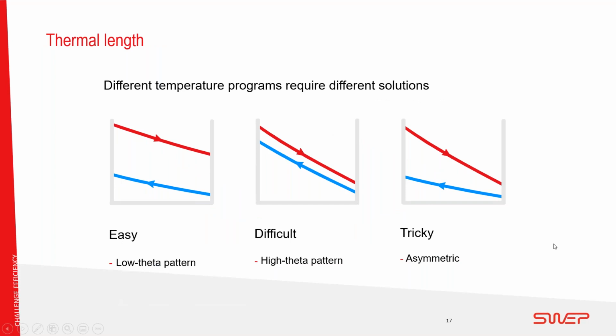So we move on to something called thermal length, and this is defined as the change in the temperature of one fluid in relation to the actual temperature difference between the two fluids. The graphs here are showing the different thermal cases that can occur, and that would require different plate patterns to meet the design whilst avoiding oversizing. A low theta pattern is generally for an easy case, which is where you'd have a small temperature change in one of the fluids or both fluids and a large temperature difference between the fluids.